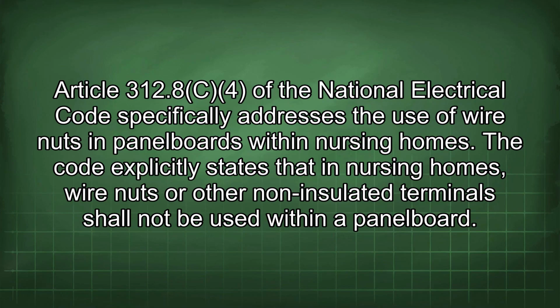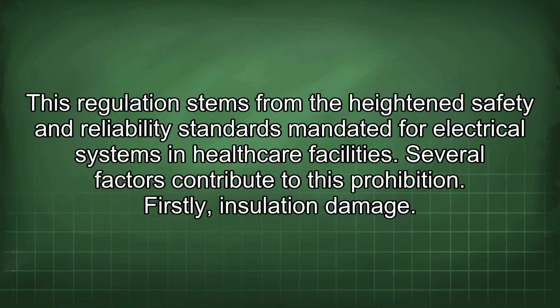312.8c4 of the National Electrical Code specifically addresses the use of wire nuts in panel boards within nursing homes. The code explicitly states that in nursing homes, wire nuts or other non-insulated terminals shall not be used within a panel board. This regulation stems from the heightened safety and reliability standards mandated for electrical systems in healthcare facilities. Several factors contribute to this prohibition.